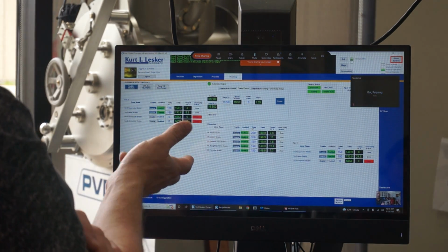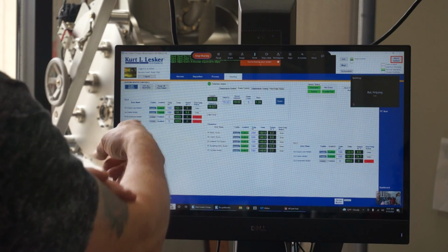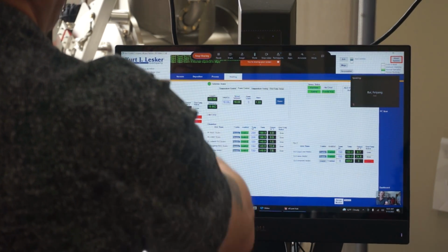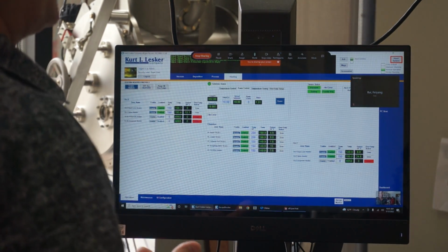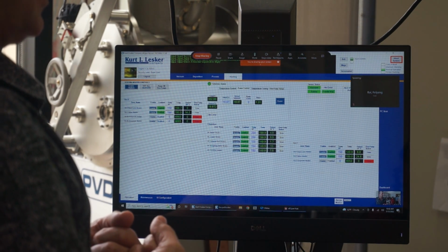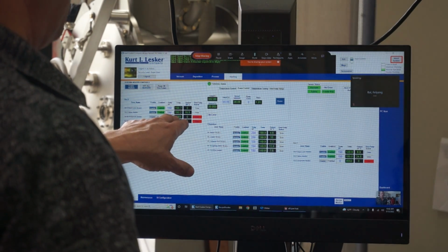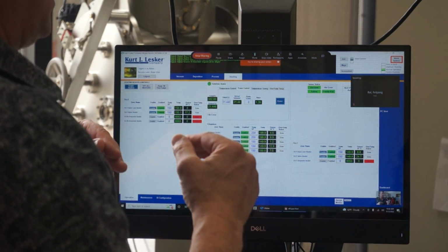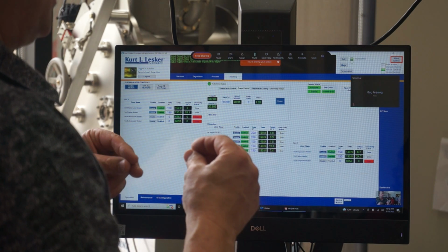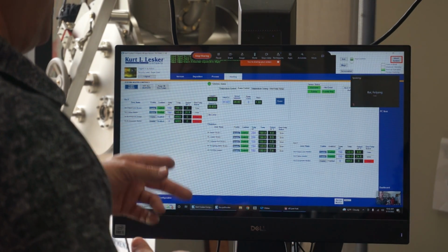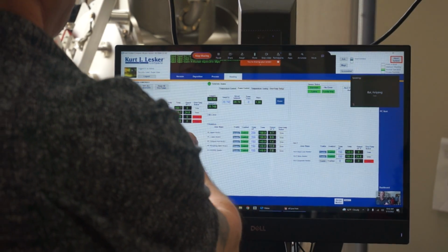Error: if one of the heaters goes out or it over temps, you'll get an error and it'll automatically shut off. This 65535 is the default, so if you have a thermocouple that's unplugged or one that goes bad, sometimes they do go bad, it'll read 65535. If there's a difference between a control and an overtemp thermocouple, or TC1 and TC2, you'll get an error. If you overtemp, you'll get an error. There's different things that can cause errors. To clear it, you just reset all overtemps.